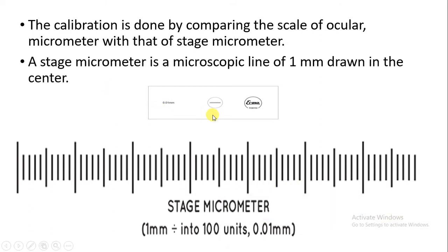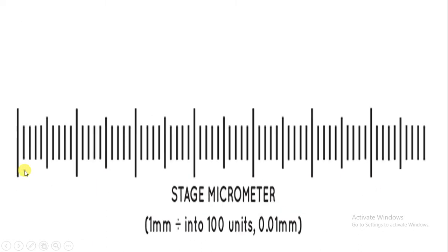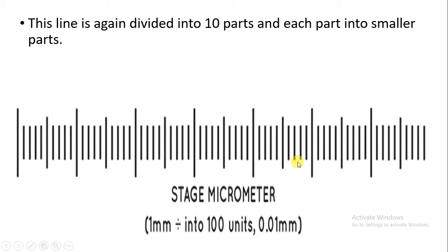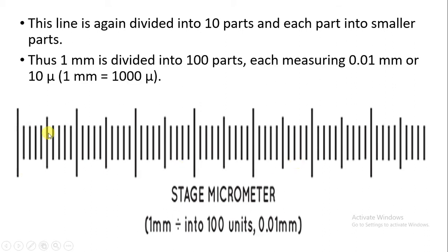The calibration is done by comparing the scale of the ocular micrometer with the stage micrometer. We need both the ocular micrometer and stage micrometer — we will coincide the lines of both to get the answer. This is the stage micrometer which has a microscopic line of 1 mm, with approximately 100 divisions. That means one division is 0.01 mm. The line is divided into 10 parts, and one division is about 0.01 mm, which you can also call 10 micron.